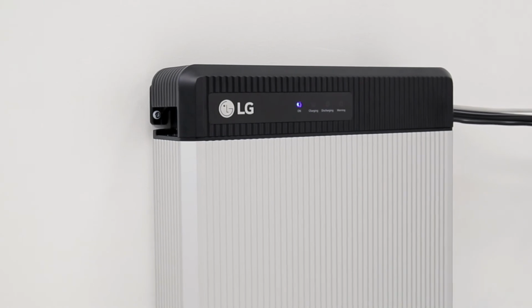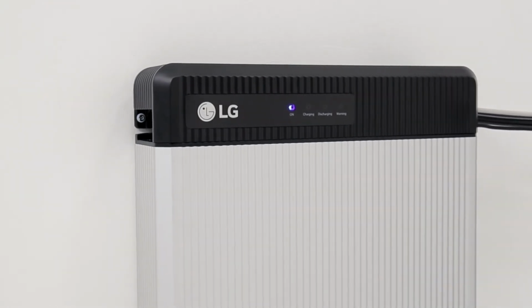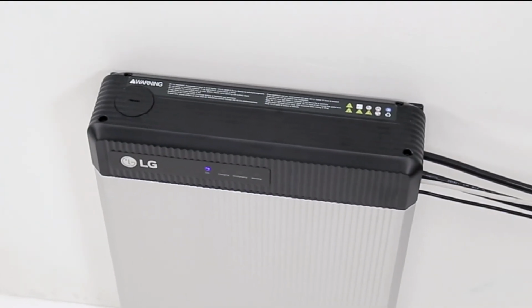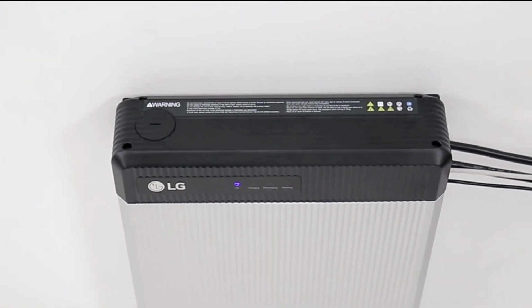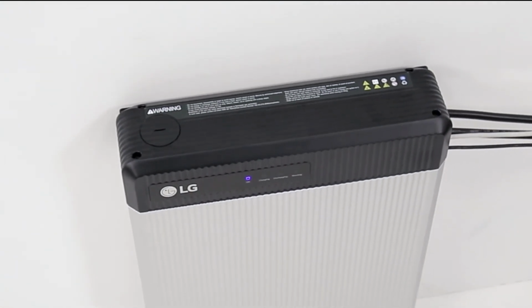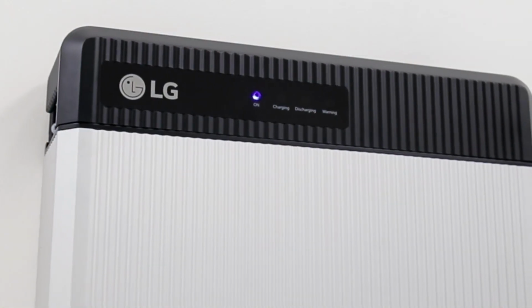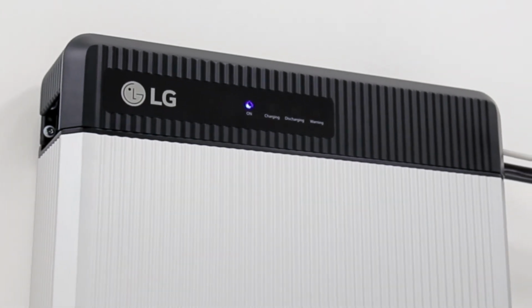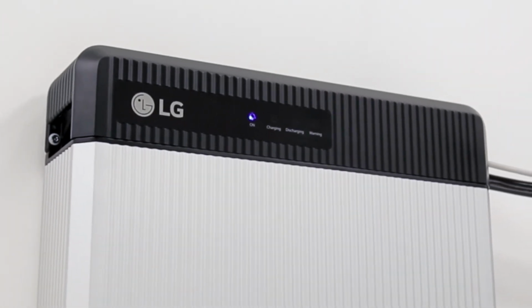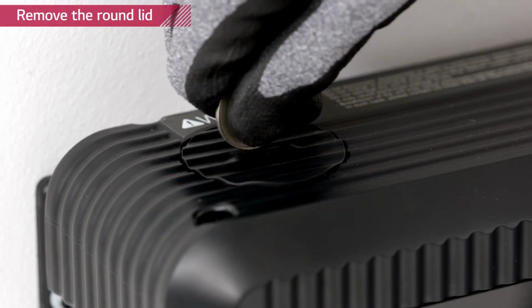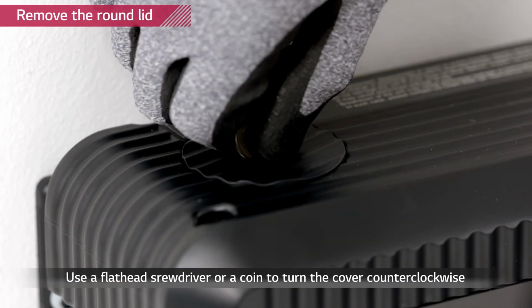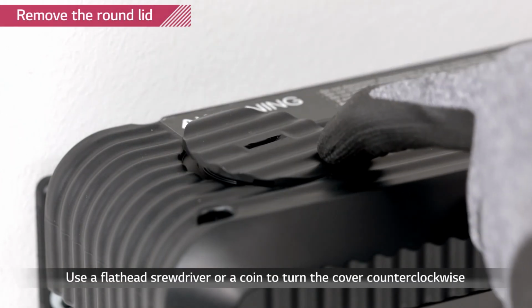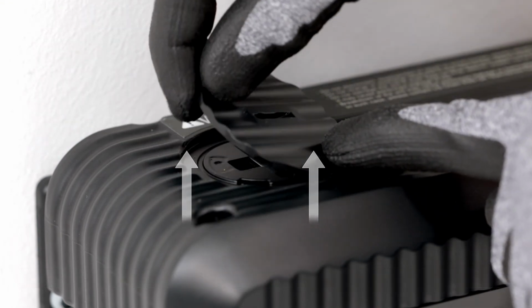If firmware update is necessary, every installer will be notified. LG Chem recommends to use one of the SD cards stated in the installation manual. Turn off the inverter. The battery pack should be turned on. Remove the round lid on the left side of the top cover using a coin. Turning it counterclockwise will allow you to loosen the lid.